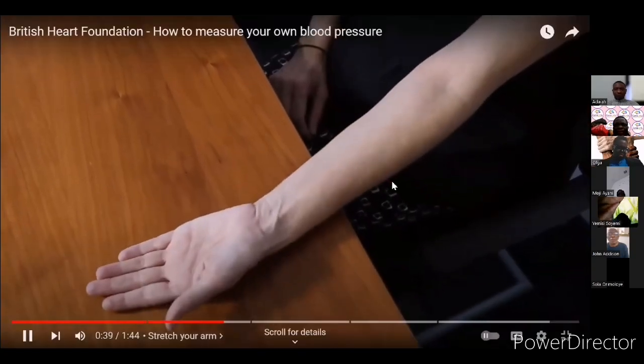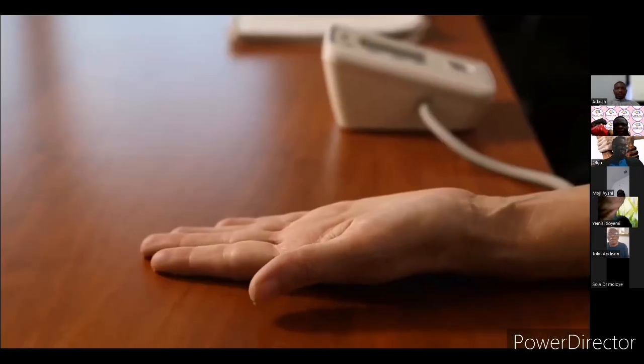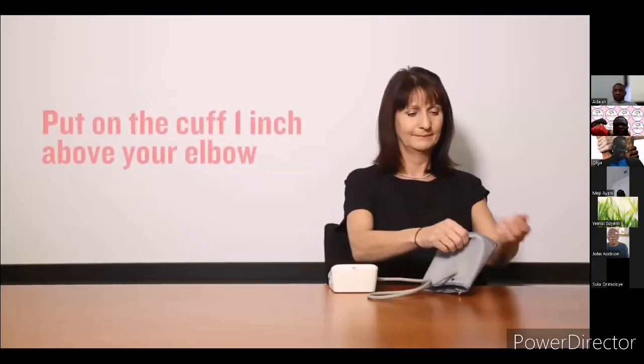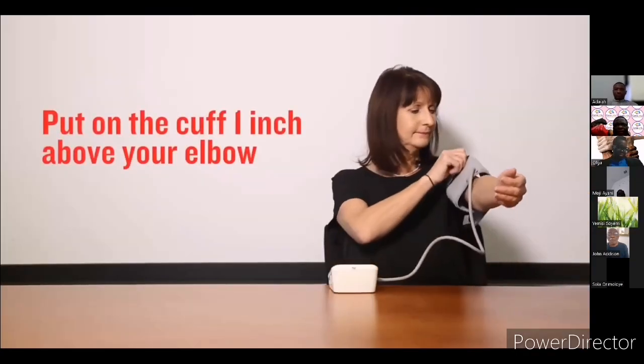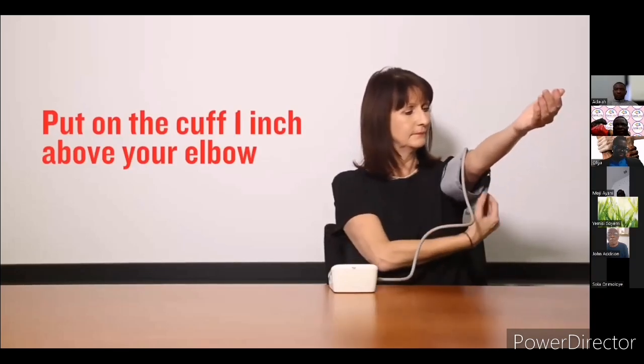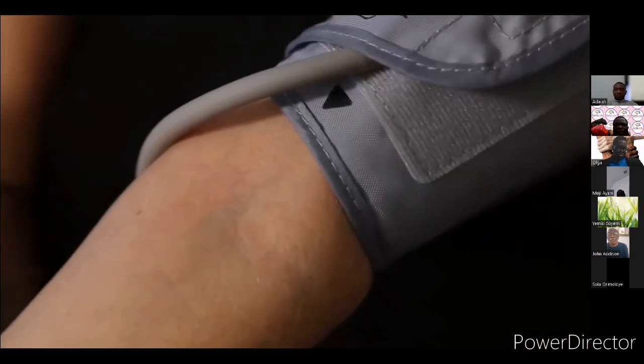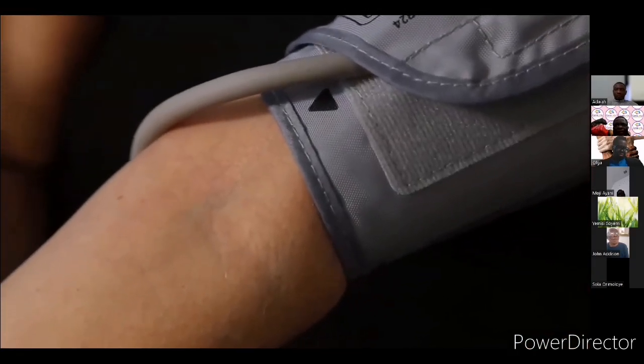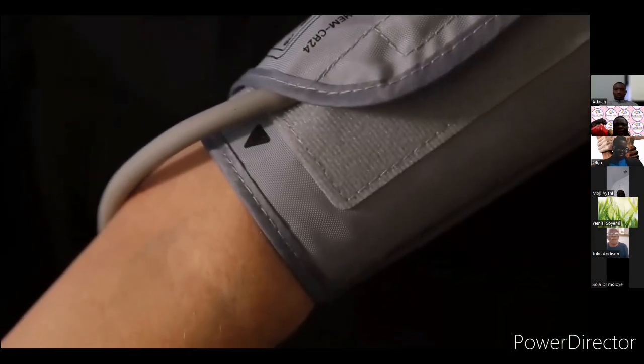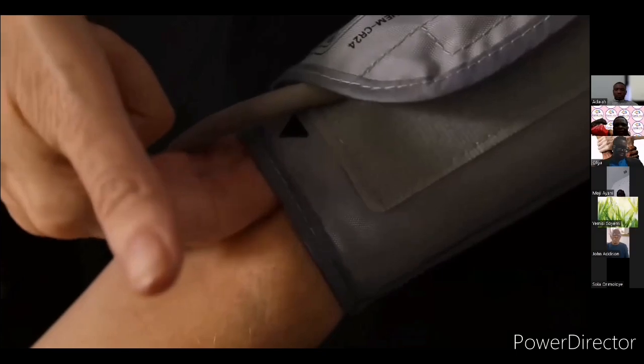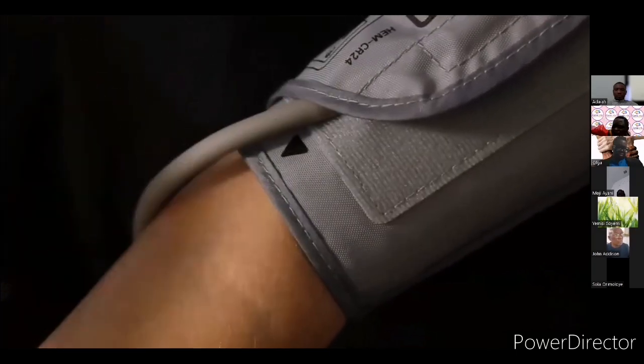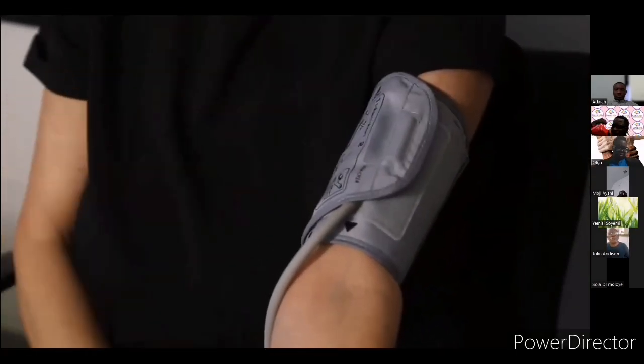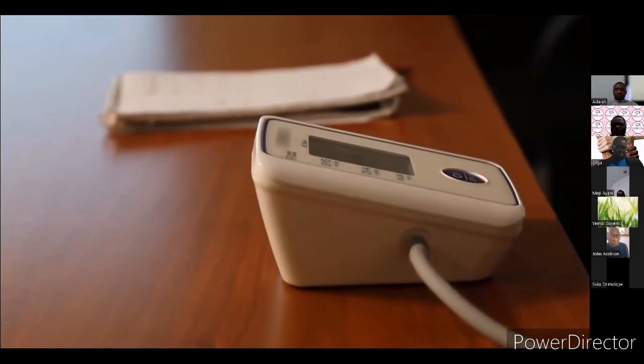Then rest your arm on the table so your forearm is about level with your heart. Stretch your arm out with the palm facing upwards. Then put on the blood pressure cuff with the bottom 1 inch above your elbow. The tubing or arrow mark should be in the center of the front of your arm. Now tighten the cuff so you can just fit in 2 fingertips, and make sure it is evenly tight at the top and the bottom. Now press start on the machine.